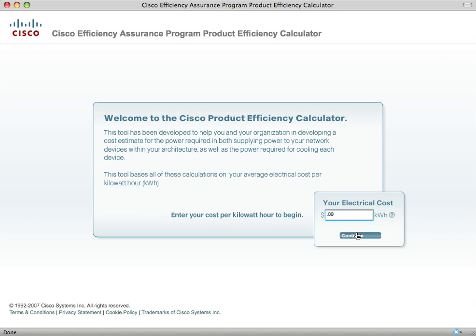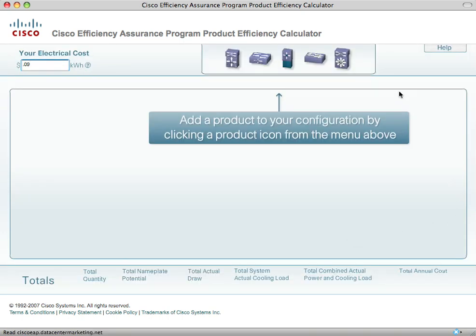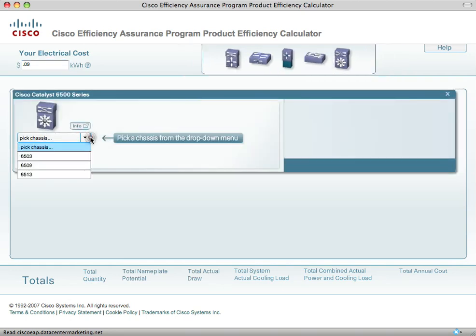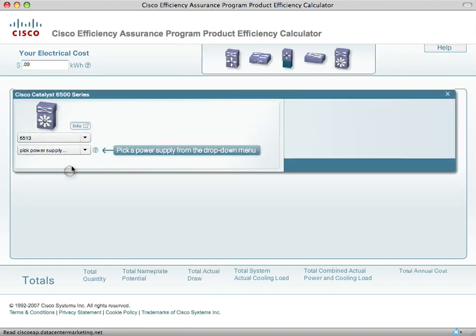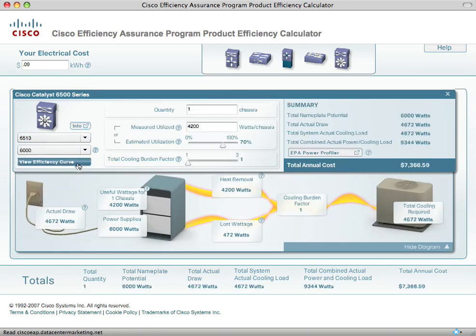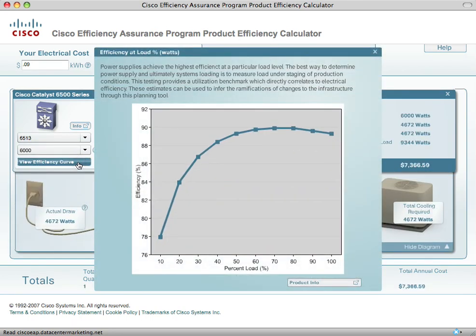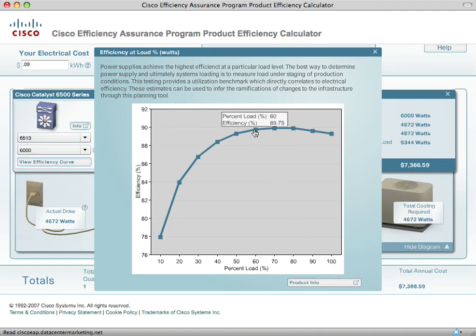We'll use an average of $0.09 per kilowatt hour for the U.S., select a Cisco product, identify the chassis configuration, and the tool defaults the power supplies that ship with that product. The first field we show is the product's electrical efficiency curve, which tells you where you need to load a product electrically to achieve its highest operative efficiency. So if we assume this is a 1,000 watt power supply, this curve tells me I need to load that somewhere between 600 to 700 watts to achieve its highest operative efficiency.